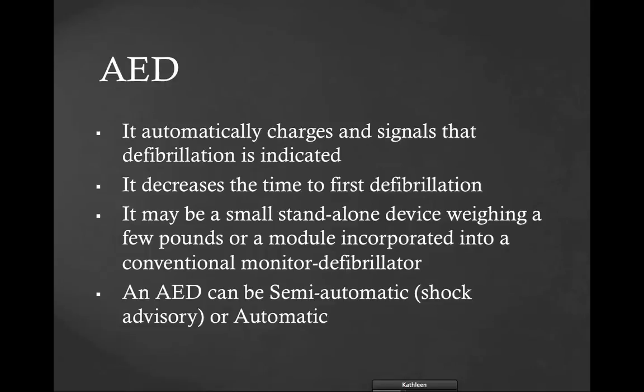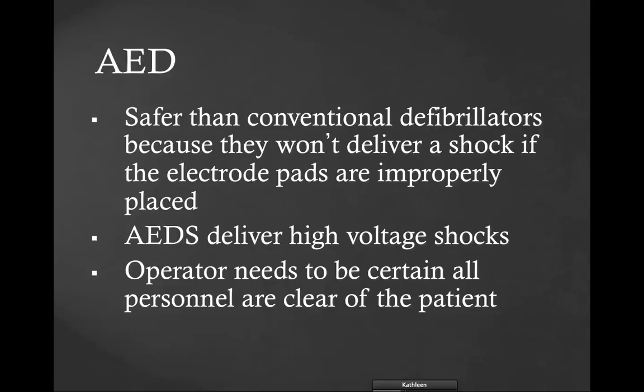AEDs have shown powerful evidence that it decreases the time to first defibrillation, which is what we want to do. An AED may be a small standalone device weighing a few pounds, or a module that's incorporated into the conventional monitor-defibrillator. An AED can be semi-automatic, which is shock advisory, or automatic. AEDs are safer than conventional defibrillators because they won't deliver a shock if the electrode pads are improperly placed.